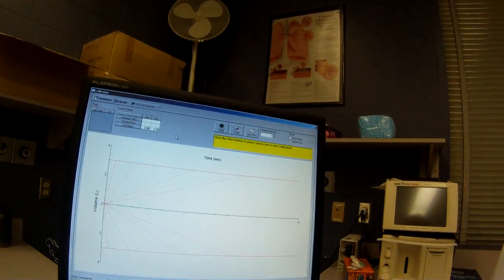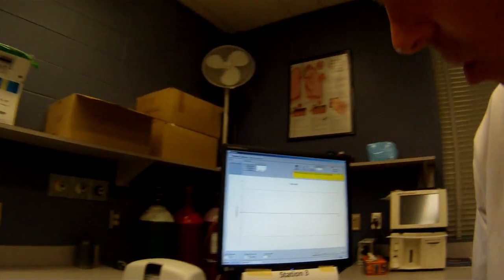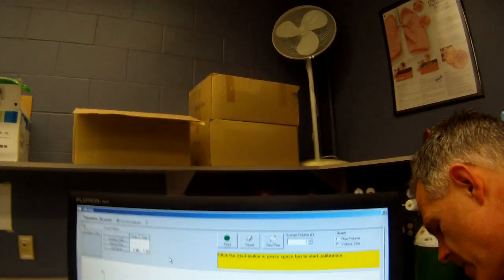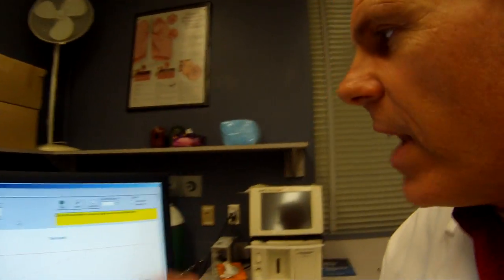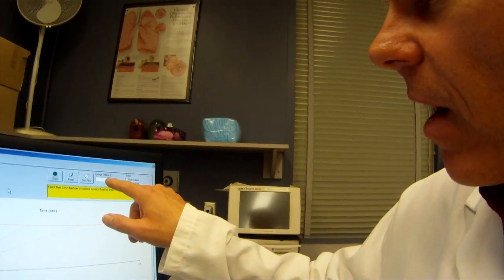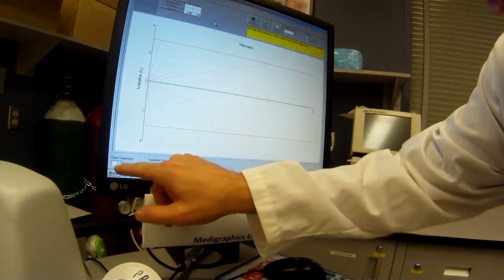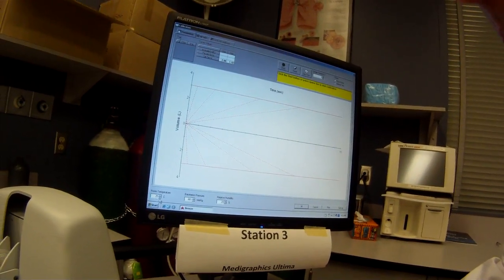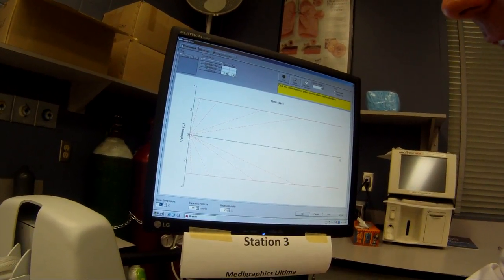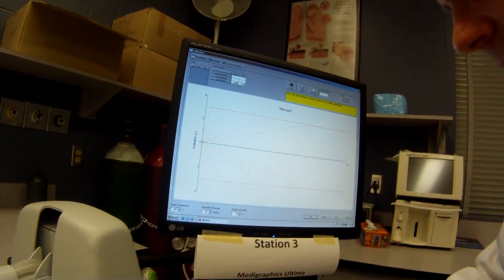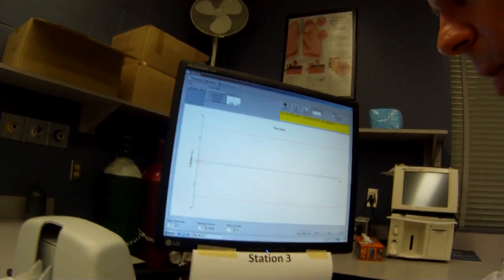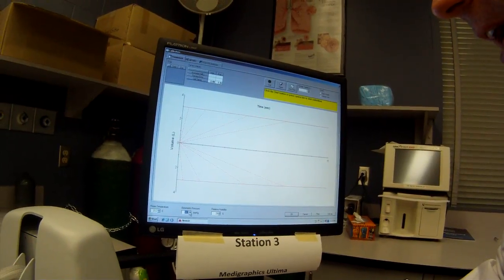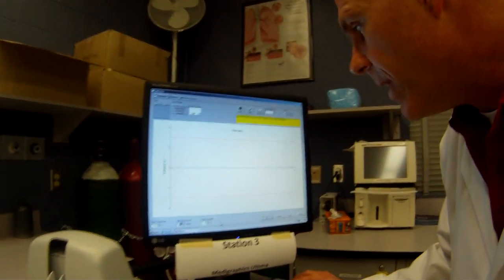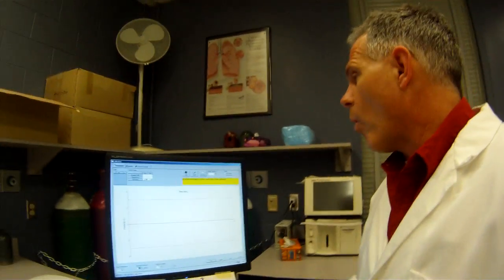All right, so what we're going to do, make sure this is all hooked up here. All right. You know what? That's probably because that isn't on there. So initially what I like to do is make sure we've got our 3-liter syringe on. We have to make sure we've got the temperature set properly for the room. So right now it's 23 degrees. I'm just going to set that back in here. It's 23.2 degrees. The barometric pressure today is 663. And the humidity is about 29%. So make sure you get those values and set those up right away.